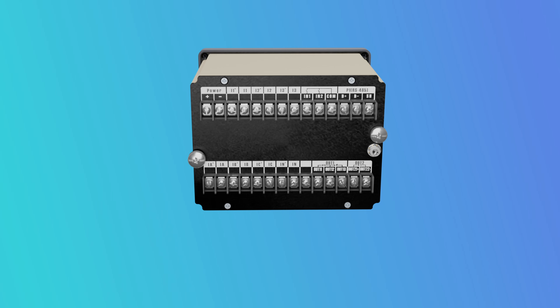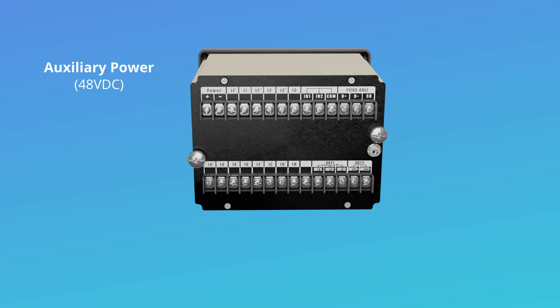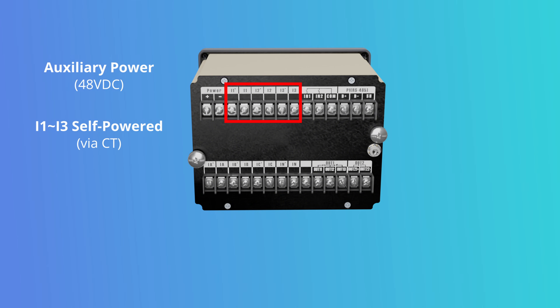Let's look at the back of the device for how the connection should be. The terminals here are for auxiliary 48V DC power supply, or the terminals for self-powered from the CT. The iRelay 50P is suitable for installation without auxiliary DC supplies, for example in ring main units or remote substations.